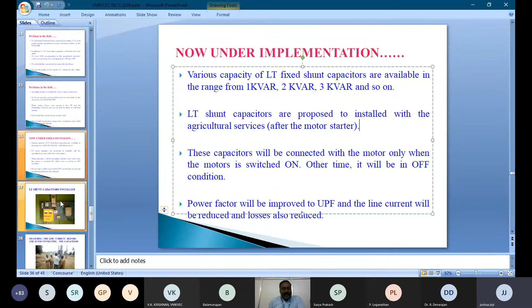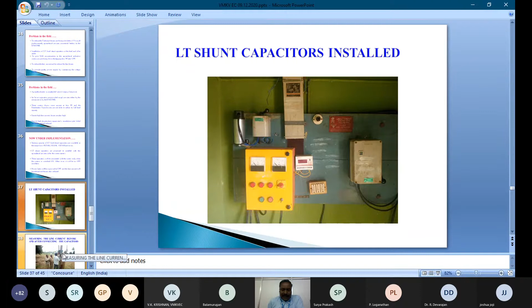We connected this shunt capacitor along with the starter, after startup. So if we switch on the motor, the capacitor will come into service; if we switch off the motor, it will be off. So whenever the motor is running, the capacitor will be included, increasing the VAR compensation and the average power factor to the unity level.